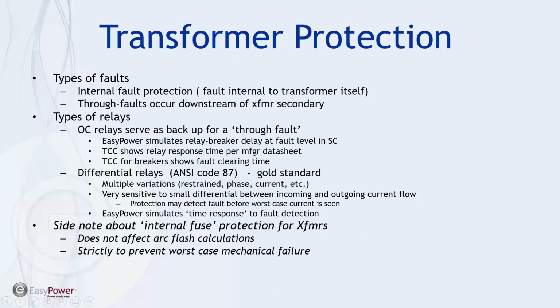The gold standard for transformer protection and overall system protection pretty much is the differential relay. And so there's multiple variations. We're going to be showing the advantage of utilizing a differential relay for main transformer protection. But it's a different setup as far as simulating what the results are.